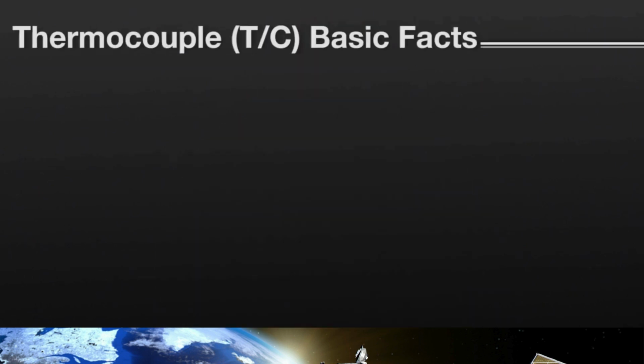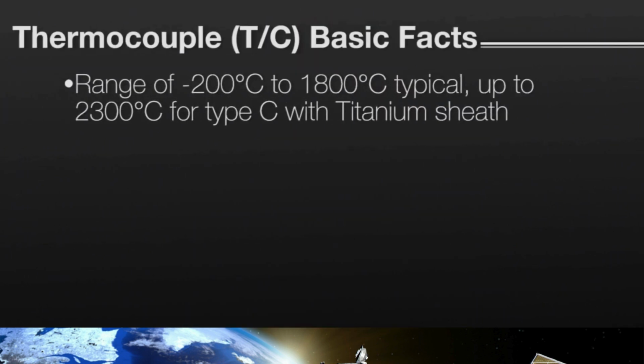And now it's time for thermocouple fun facts. The measurable temperature range varies greatly by which alloy pairs you pick. One pair of obscure alloys known as a Type C thermocouple will accurately measure temperature up to 2,300 degrees Celsius as long as you use a titanium sheath to protect it.